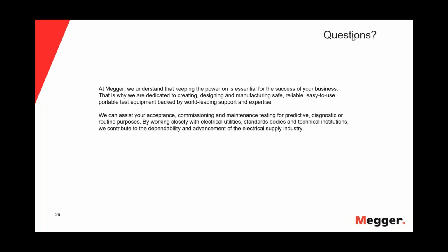Thank you, Javier. Henning, can partial discharge detect the water ingress in the straight cable or joint? Is partial discharge sensitive to water ingress or a water tree? Okay, we have to go back to what does partial discharge mean. Partial discharge is when you have a discharge in a gas, could be in air, could be in other gases.